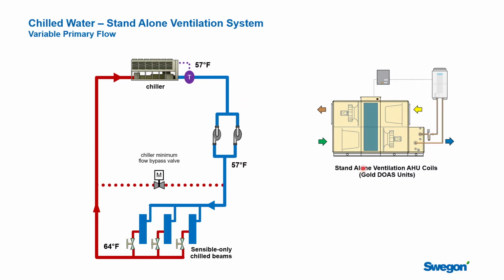Over on the ventilation system, you make this a standalone piece of equipment. So it would have integrated heating and cooling. It'd be great if you had a heat pump system, because then it'd be kind of a carbon-free solution. You're not burning any natural gas. Now this piece of equipment, its efficiency is going to be less when it's hot outside, right? This is effectively now air-cooled DX versus a nice big fancy chiller plant, but this load drops off very quickly and is quite linear to your outdoor air conditions.